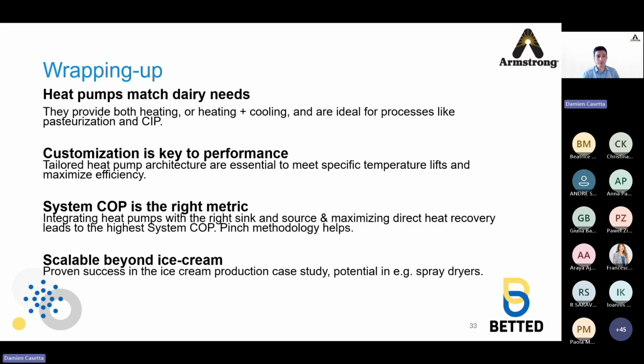Okay, time for a wrap up. So we've seen that heat pumps match dairy needs. They basically provide heating or heating and cooling and are ideal for processes like pasteurization and cleaning in place. Customization is key to performance. Tailored heat pump architectures are essential to meet specific, large temperature lifts and maximize efficiency. The system efficiency, the system COP, is the right metrics. Integrating heat pumps at the right sink and source and maximizing direct heat recovery leads to this highest system COP. For this, the pinch methodology helps.